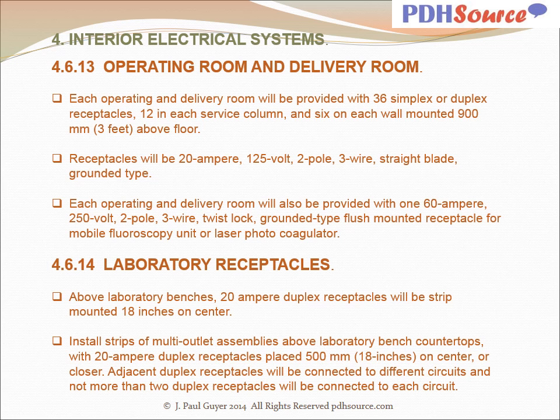Each operating and delivery room will be provided with 36 simplex or duplex receptacles, 12 in each service column and 6 on each wall mounted, 3 feet above floor. Receptacles will be 20 amp, 125 volt, 2 pole, 3 wire, straight blade, grounded type. Each operating and delivery room will also be provided with 60 amp, 250 volt, 2 pole, 3 wire, twist lock, grounded type, flush mounted receptacle for mobile fluoroscopy unit or laser photo coagulator.